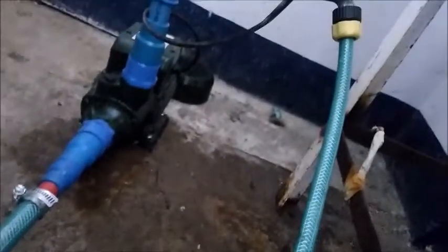As you can see, we are now testing the pump. First we applied water pressure to the hose, which will serve as a jump start in order for the water to flow to the piping network. As you can see, the flow rate of the water is constant. And so this is the first testing after we have prepared the pipings on the chilled water system and also replaced the pump.